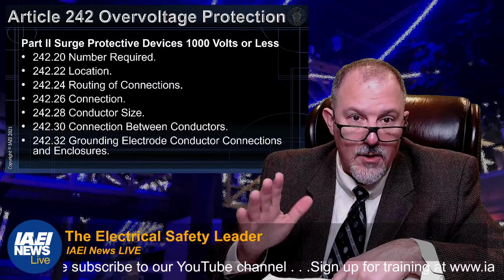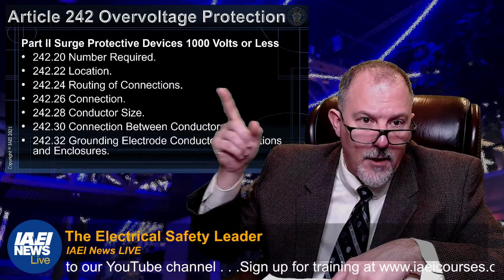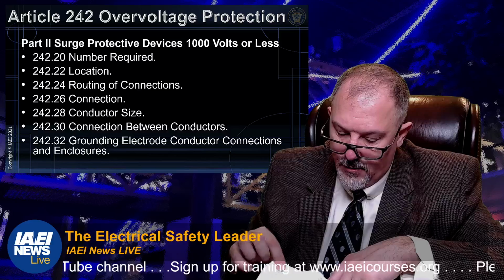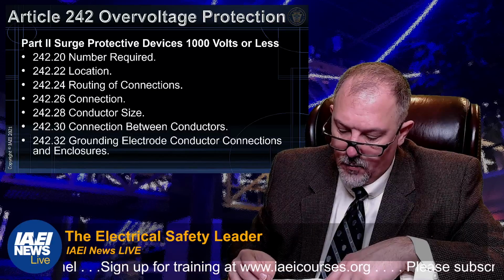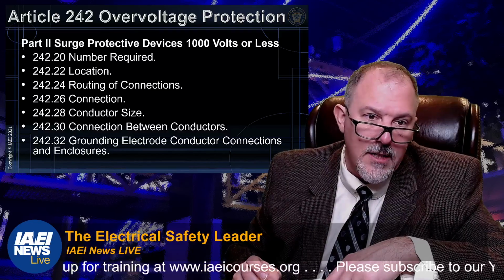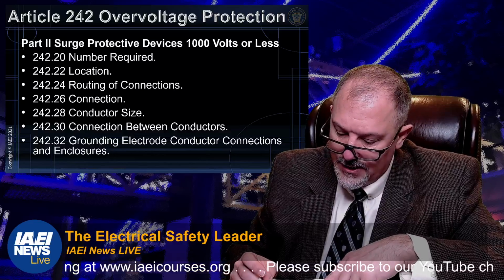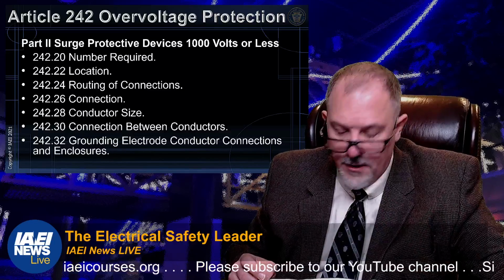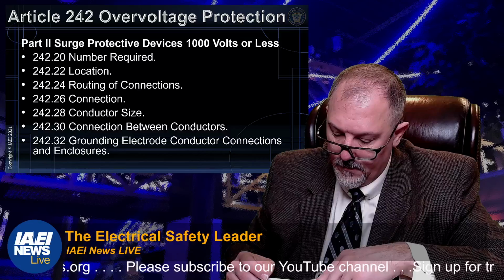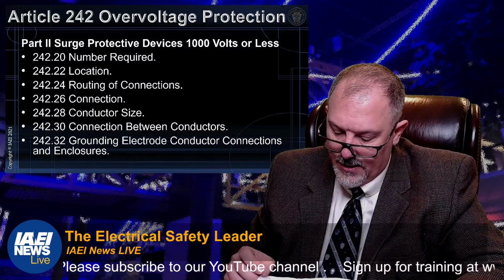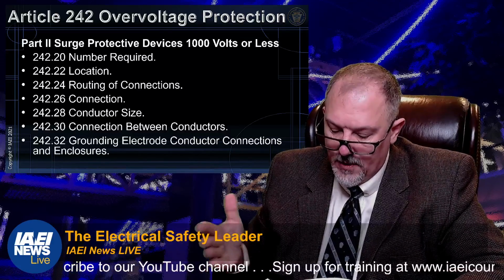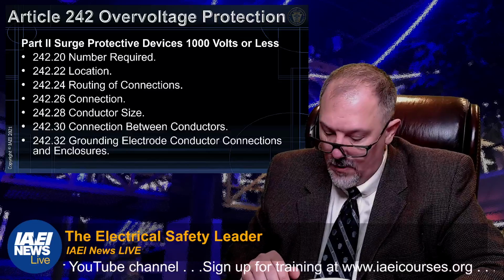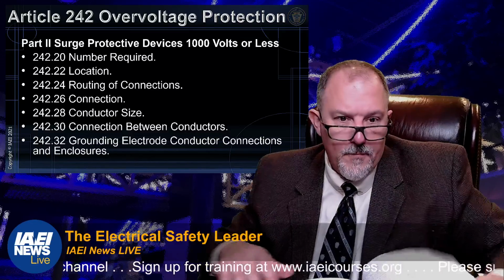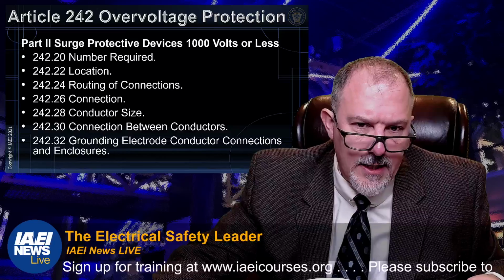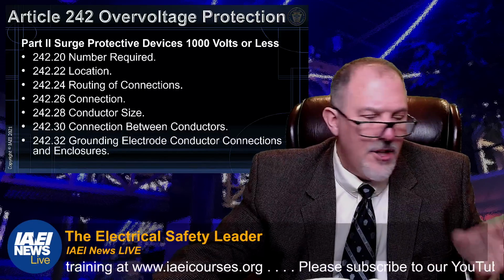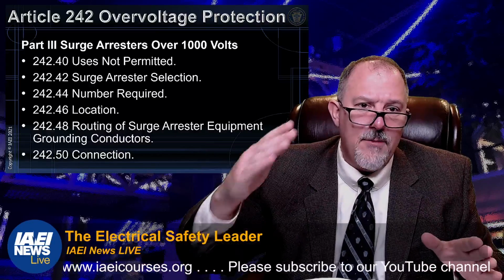Right? See, these are all in Part 2. You have the number required. You have the location, permitted to be located indoors or outdoors. And you have the routing of connections. Then you have the connection itself. And they reference other sections in the code. In conductor size, the line and ground conductor shall not be smaller than a number 14 or a number 12. And then there's dot 30, connection between conductors. So they're going through each of these, and that was under 1,000 volts.